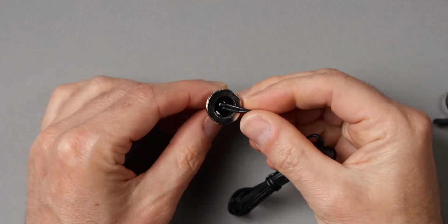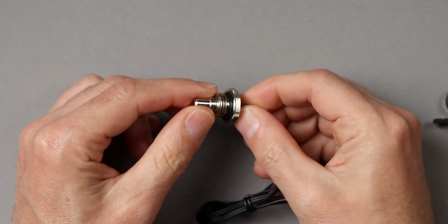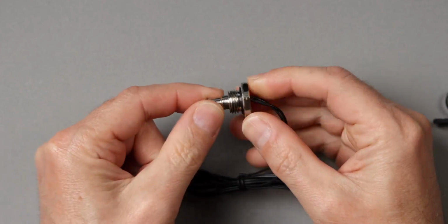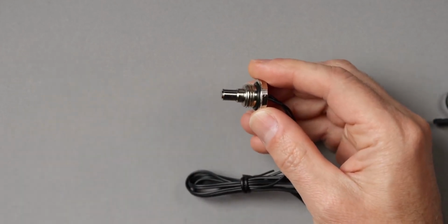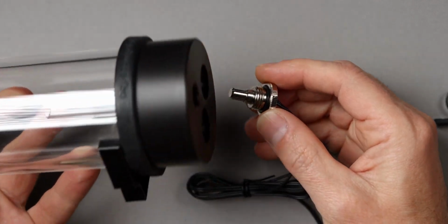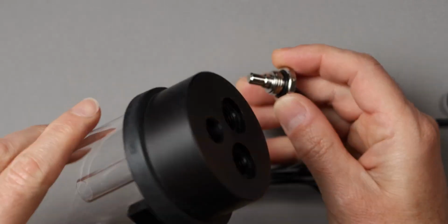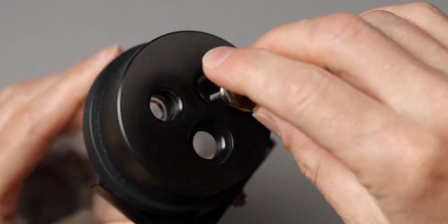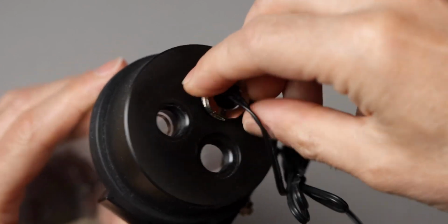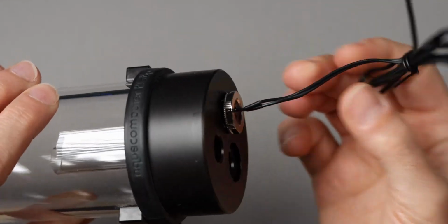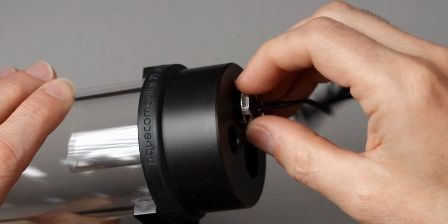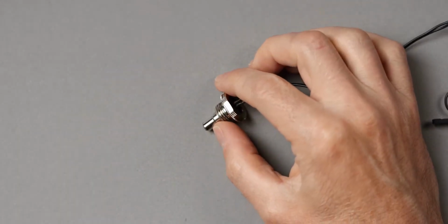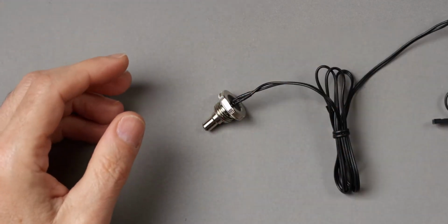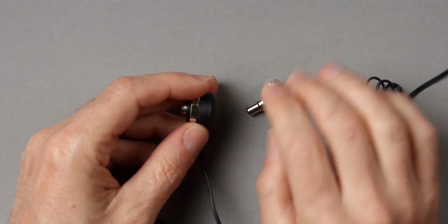The other type is more of a probe-shaped kind of model. It has the temperature sensor out here in the tip. This kind is mounted in an unused port, like in this reservoir. Just make sure it touches the water. It could also be a port in a radiator or a spare port in the pump housing. So where should you place the sensor? With the probe type, you might only have a few options. But as I said, this ring type can fit in everywhere.